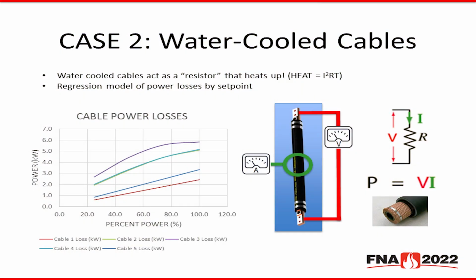The graph on the left shows the power drop by percent power. So the purple line at the top, for example, shows that at 80% power, this cable is continually dumping about 5.5 kW into the water, whereas at 40% power, it's 4 kW. Remember that water-cooled cables are just a resistor wrapped in water. And so this introduces the value proposition of reducing that high current circuit outside of the hot zone to improve electrical efficiency within a system.